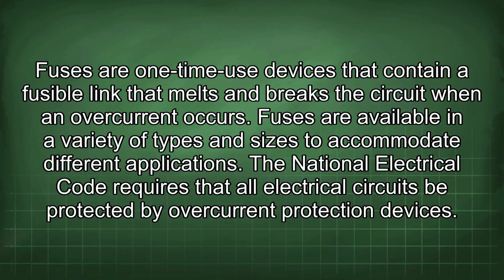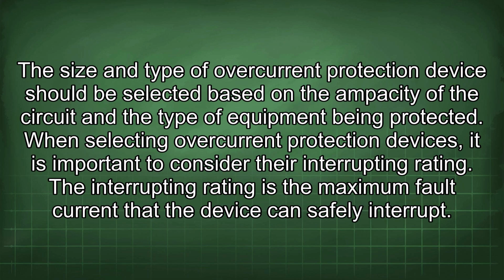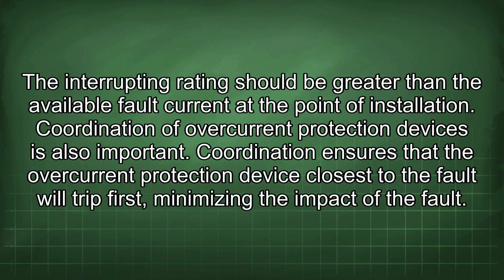The National Electrical Code requires that all electrical circuits be protected by overcurrent protection devices. The size and type of overcurrent protection device should be selected based on the ampacity of the circuit and the type of equipment being protected. When selecting overcurrent protection devices, it is important to consider their interrupting rating. The interrupting rating is the maximum fault current that the device can safely interrupt. The interrupting rating should be greater than the available fault current at the point of installation.